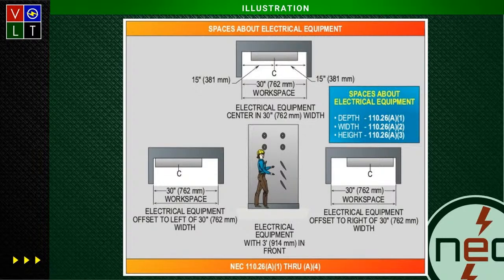All right, it's Lemonhead. Now, when we start looking at this, basically when you go over and look at 110.26(A)(2), this is where you get the width of the equipment telling you that you've got to have at least a 30-inch workspace.